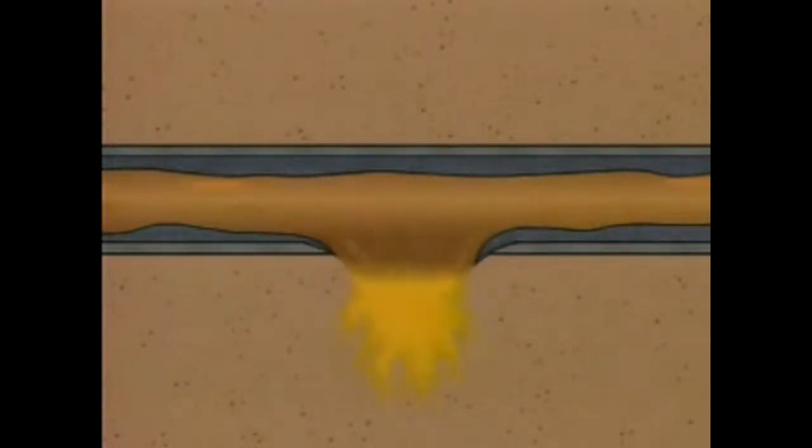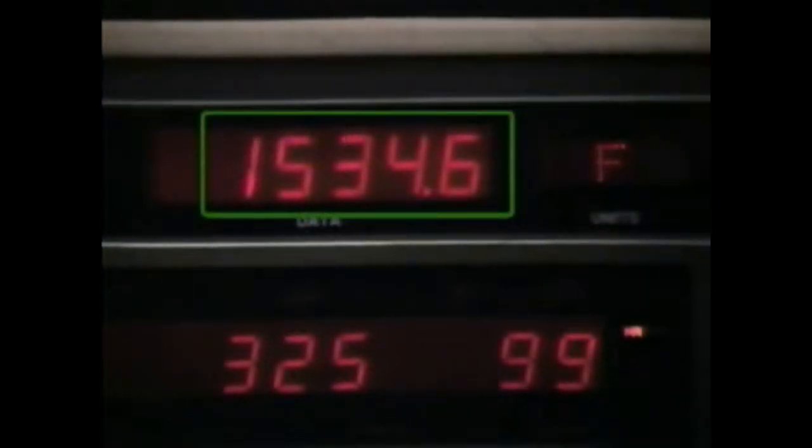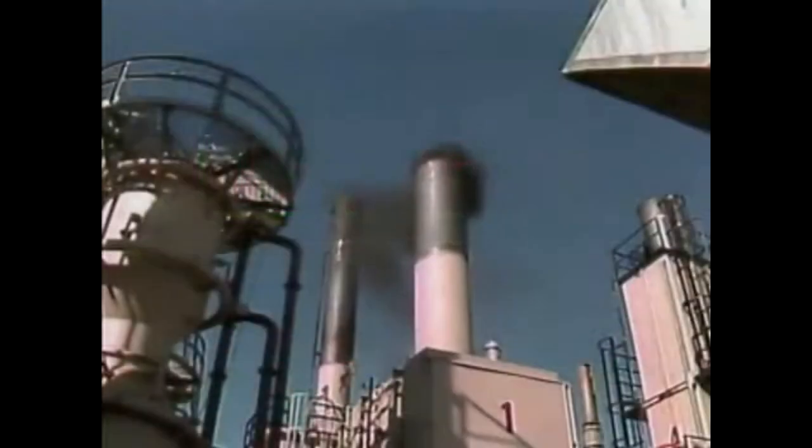When a tube ruptures, any flammable process fluid that escapes is likely to catch fire in the furnace. A high stack temperature is one sign of burning process fluid. Smoke coming from the stack is another. When there's a tube leak, you may also see smoke coming from the tube access doors. But if you do, don't open the door. The sudden rush of air could cause a flash fire.